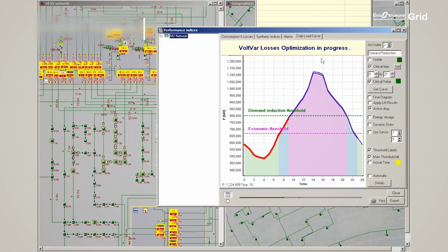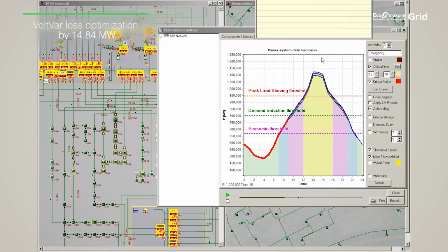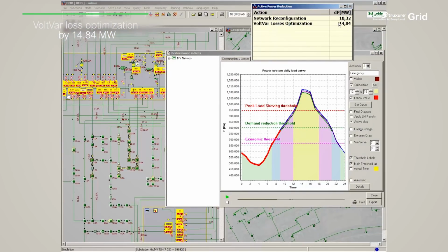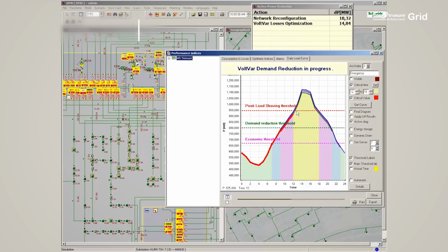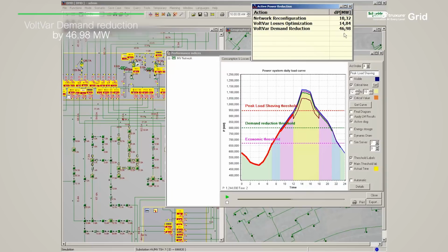In our example, VoltVar loss optimization reduces the load by almost 15 megawatts. And for peak load shaving, VoltVar optimization in demand reduction mode reduces load by nearly 47 megawatts.